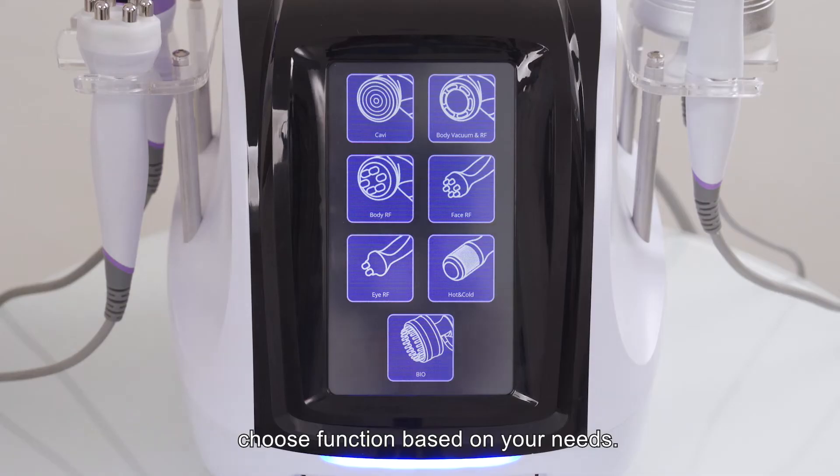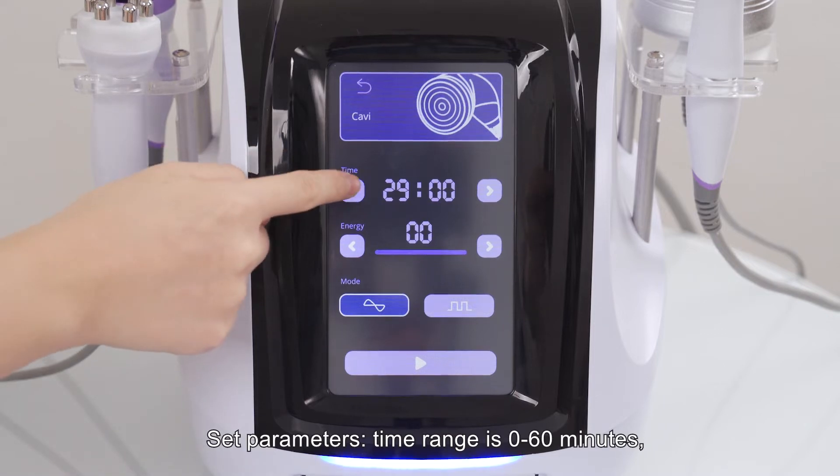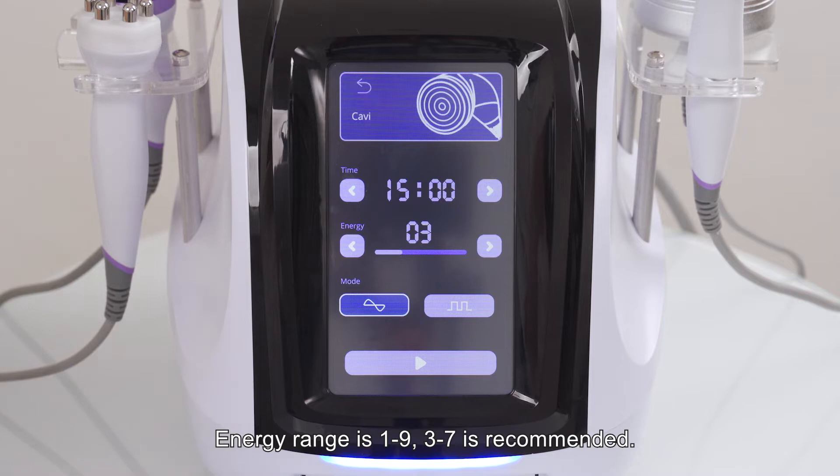Choose a function based on your needs. Press the Cavi function button and set parameters. Time range is 0 to 60 minutes; 15 to 20 minutes is recommended. Energy range is 1 to 9; 3 to 7 is recommended. Constant working mode is recommended.